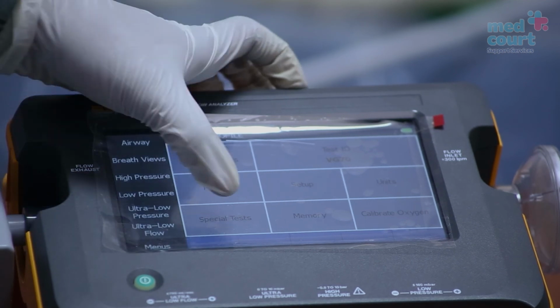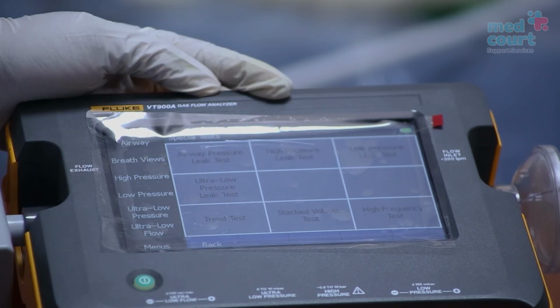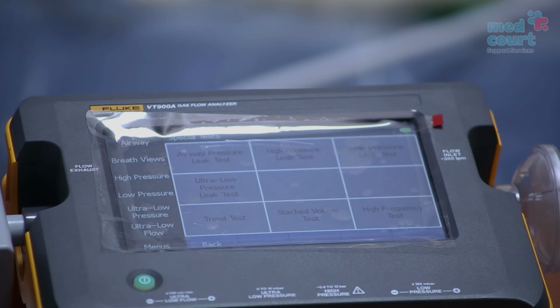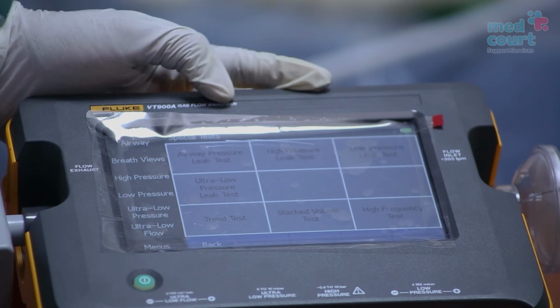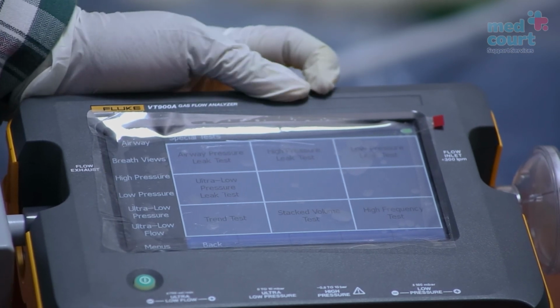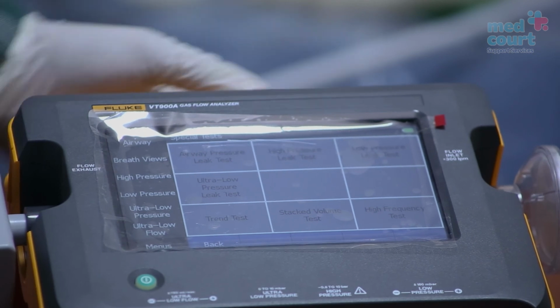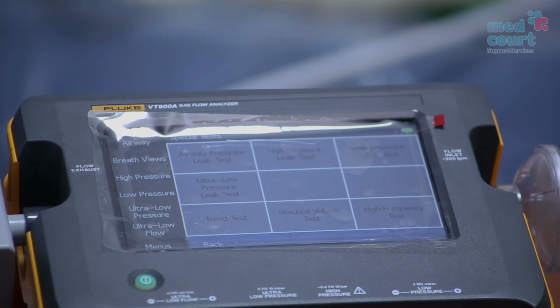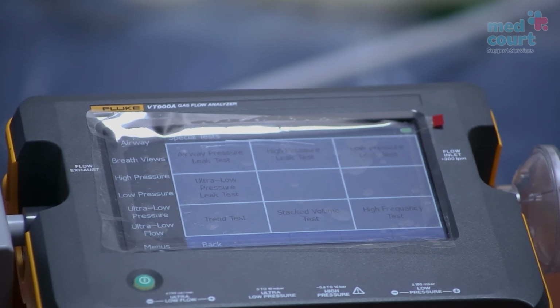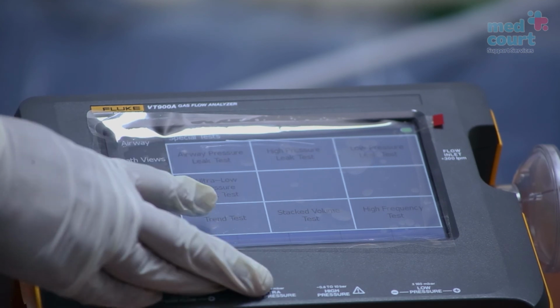In addition to the special tests mentioned previously, there is also the stacked volume test, the high frequency test, the ultra low pressure leak test, the airway pressure leak test, the high pressure leak test, and the low pressure leak test. These tests are more common with the anesthesia machines, but since we are using the ventilator, we only checked the trend test.